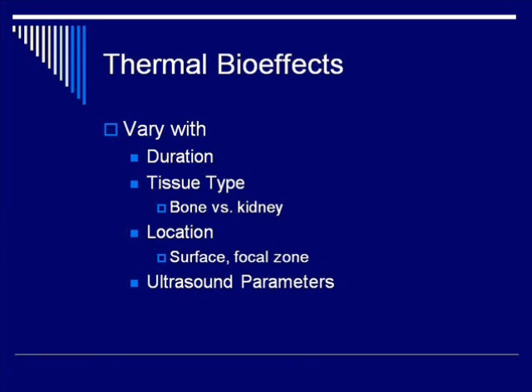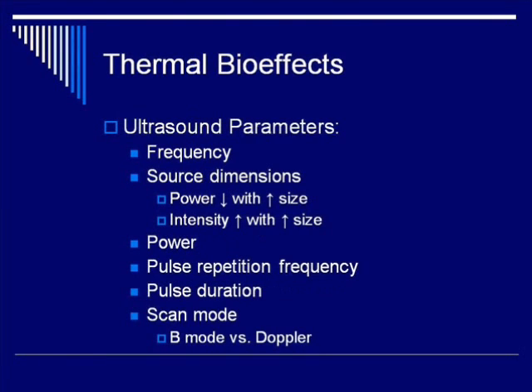Location will change the characteristics of attenuation as well. Recall that you have the most ultrasound at the surface, so you will have more attenuation and heating at the surface. The other place where you will have a lot of ultrasound attenuation and therefore a lot of heating is at the focal zone, another area of high intensity, as we've discussed earlier. And finally, a variety of ultrasound parameters can affect thermal bio-effects.